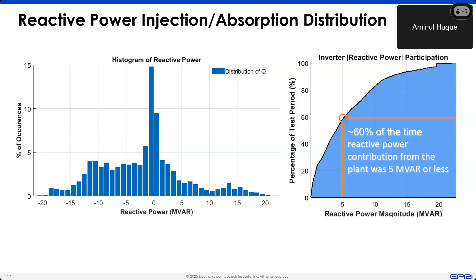The last thing I wanted to highlight, and this is important: when this particular plant was designed and constructed, I don't think nighttime reactive power was in the scope. It was maybe an afterthought for research purposes. We did it for a couple of months and then stopped and went back to normal operation. It was not designed from the get-go for nighttime reactive power support, but the inverter selected for this project had the capability, and the utility worked with the plant owner to come up with a project scope and activate this capability.